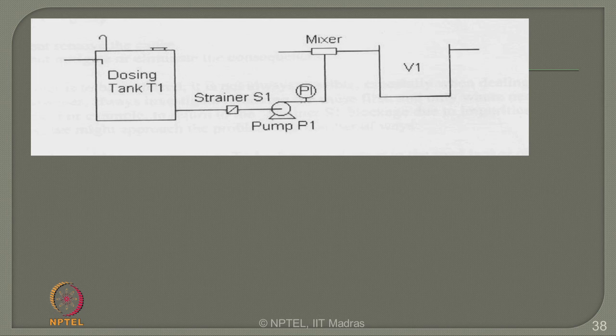Let us take an example here. There is a dosing tank T1 which has to supply some chemical mixture to the container V1, and the container also receives chemical from a mixer as a third line. Now, the dosing tank T1 has two components mixed together, and these components can even contain floating suspended particles. Therefore, I use a strainer S1 to filter the suspended particles, and of course, I have to pump this chemical to the container V1, therefore, I require a pump P1. Now, the components identified here are the dosing tank T1, the strainer S1, which is nothing but a filter, the pump P1, the mixer and the container V1.